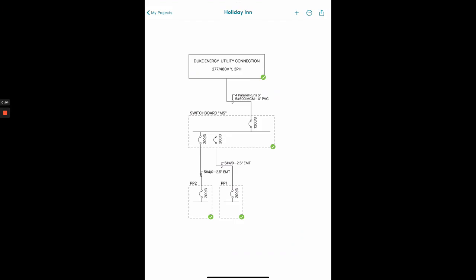The next thing we're going to do inside Conduit is adding a transformer. So we've got switchboard MS here. It's a 277/480 volt Y switchboard. We need to add a transformer because we need to step some of this voltage down to 120/208.